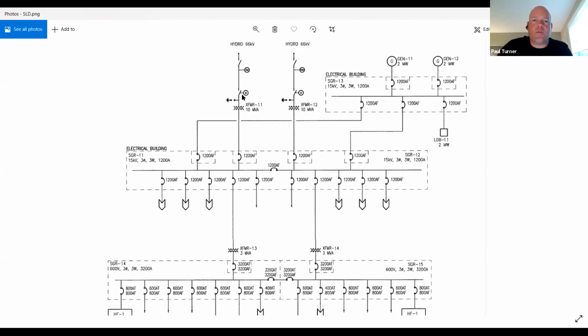That would start with some coordinated testing with the utility. The 66 kV feeds, the main disconnects here, would be closed to first energize the pair of 10 MVA transformers. These would be large oil-filled transformers, 10 MVA, that would step down the 66 kV voltage down to 15 kV voltage.